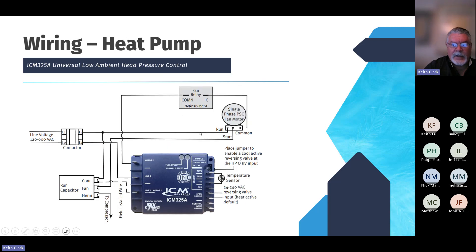Same wiring for a heat pump, with one difference: T2 goes to line 2 again, and the common from the capacitors goes to L1 or line 1/motor 1 on the control. Then the motor 2 terminal, instead of going to the common terminal on the motor, goes to the common terminal on the fan relay or defrost board. You've also got the jumper for cool-active if you want to change that, temperature probes, and the reversing valve input.